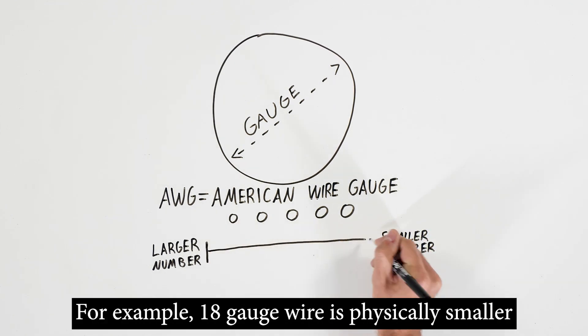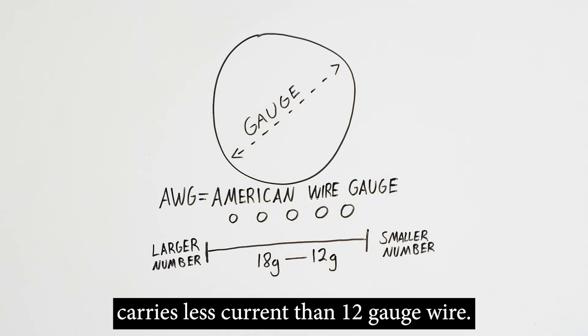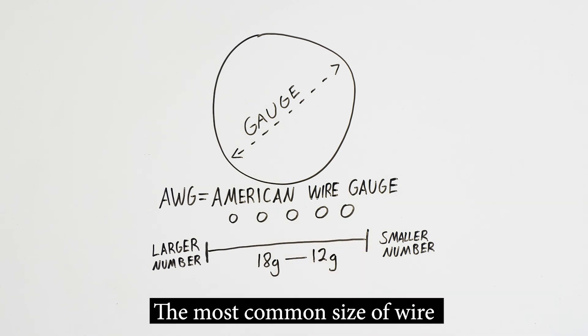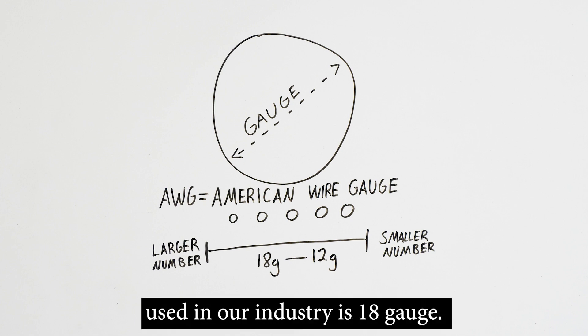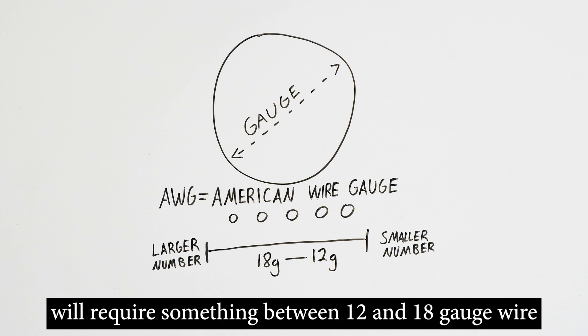For example, 18 gauge wire is physically smaller than 12 gauge wire, and therefore, 18 gauge wire carries less current than 12 gauge wire. The most common size of wire used in our industry is 18 gauge. Almost every electrified hardware installation will require something between 12 and 18 gauge wire.